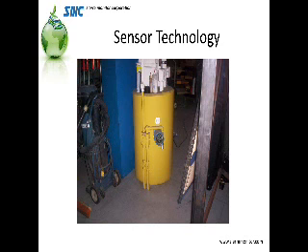Now here we see a combustible type technology used in an LNG facility. You'll notice the sensor is located off the floor. The engineer's requirement here was that LNG could cool before it would actually expand to a gas and go to the ceiling. They wanted to indicate if there was gas as quickly as possible. So they had the sensor mounted at about 18 inches from the floor.